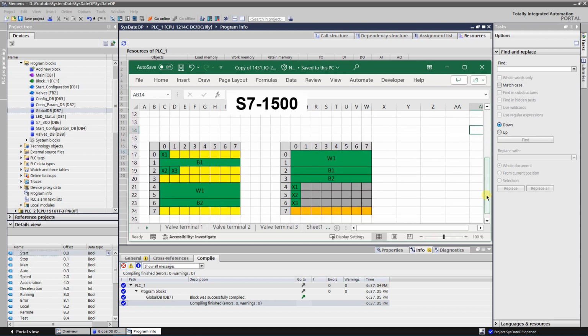Here is the setup of S7-1500 series. Again, no gaps are formed since larger tags are located at the beginning of the block and smaller ones at the end. Very fast access is granted, as tags are stored in a way so that the processor can directly read or write all tags with just one machine command. Boolean tags are stored as byte. It enables faster access as the controller therefore does not have to mask the access. The architecture of the CPU supports little endian sequence, and always accesses 4 bytes.